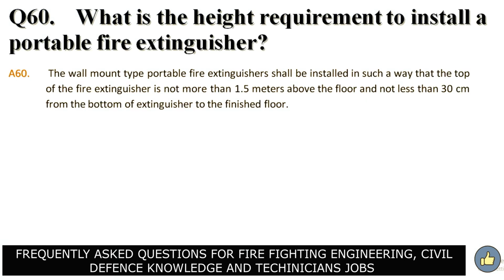What is the height requirement to install a portable fire extinguisher? Answer. The wall mount type portable fire extinguisher shall be installed in such a way that the top of the fire extinguisher is not more than 1.5 meters above the floor and not less than 30 centimeters from the bottom of the extinguisher to the finished floor.